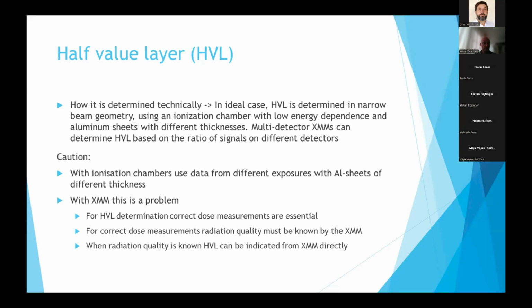And here I want to mention that you shouldn't use an XMM with aluminum filters to calculate HVL, because indications of XMMs are very, very dependent on radiation quality. And of course, if you add aluminum filters, you are changing radiation quality. Beam hardening is happening. So in that case, you can get a very, very wrong result.